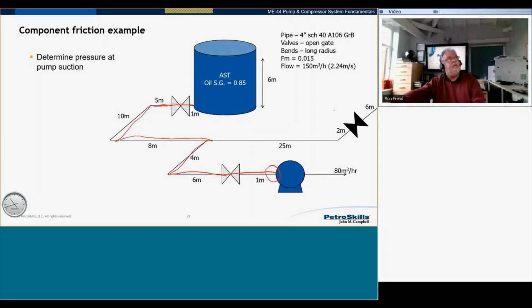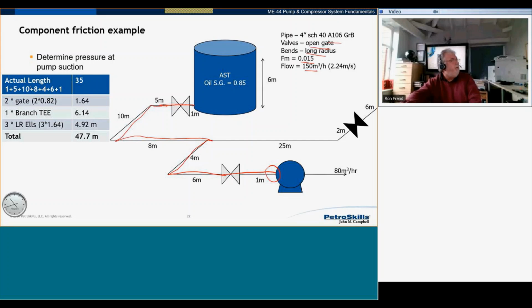all I now need to know is what's going on here. So I know it's a 4-inch Schedule 40 A106. The valves are all open gate. The bends are long radius. I've been given the friction factor, and I know the flow. All I do, first of all, is add up all the actual lengths. So 1 plus 5 plus 10, and so on, gives me 35 meters. I know I've got 2 gate valves. I've got one here, and I've got one right there. 2 times 0.82, 1.64. Same for a branch T, the same for 3 long radius elbows. And these are all of those equivalent lengths. The total adds up to 47.7 meters.